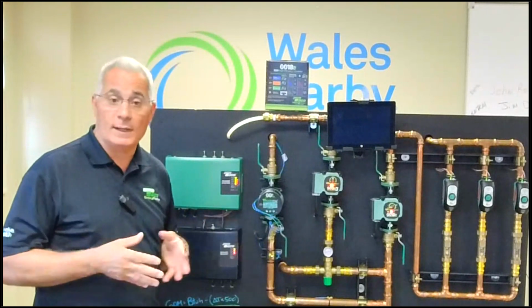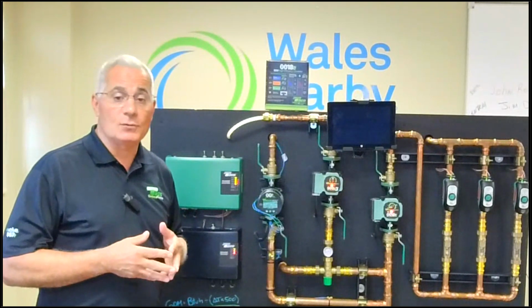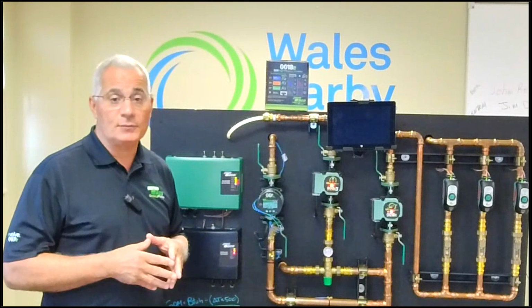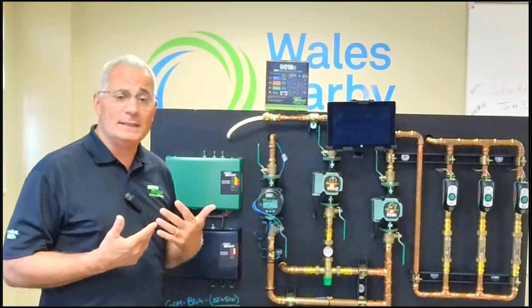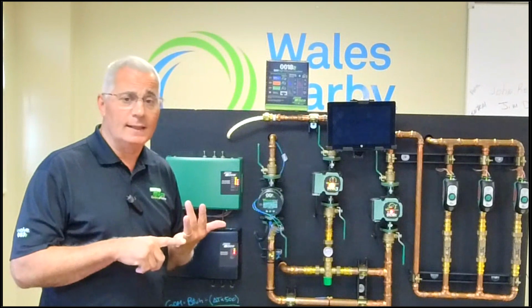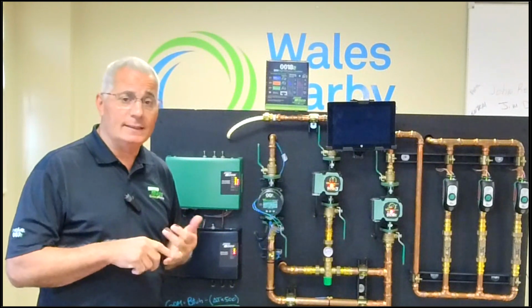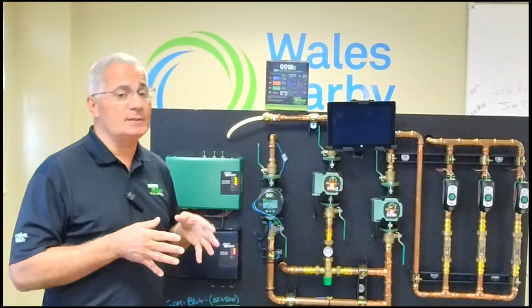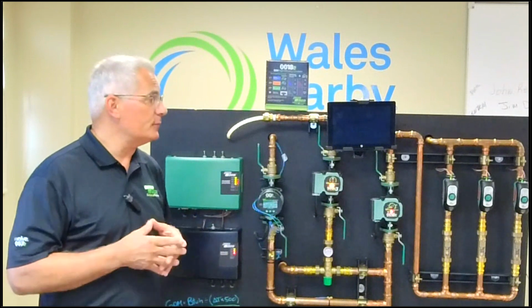If I did, then I could wire it there, and when that zone called, the other space heating zones would have to wait. But if I want the ability to deliver space heating and also the radiant, then I want to put that circulator on a separate relay, so they're independent from each other.